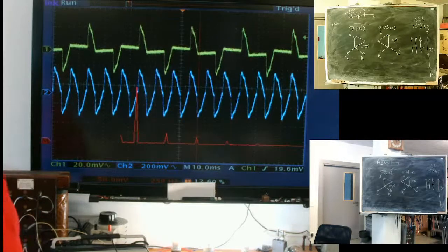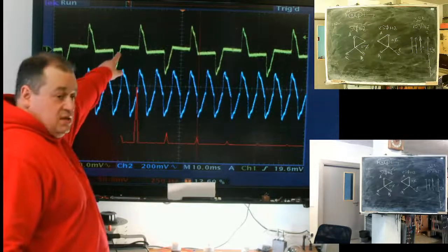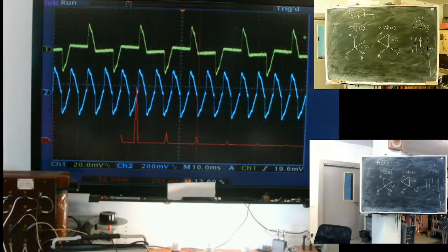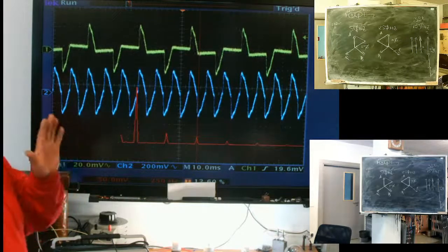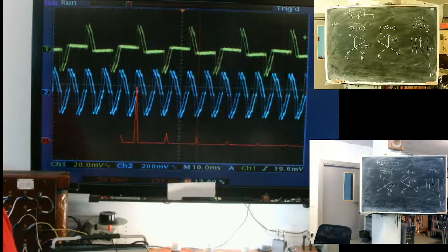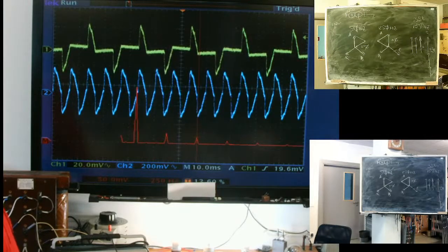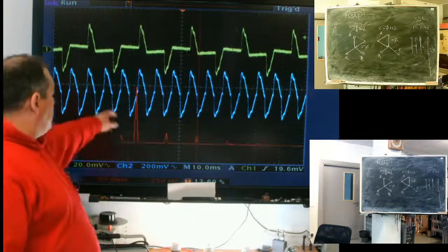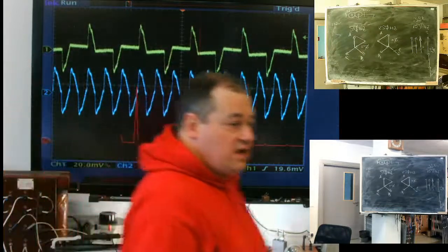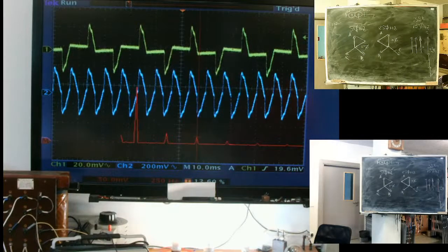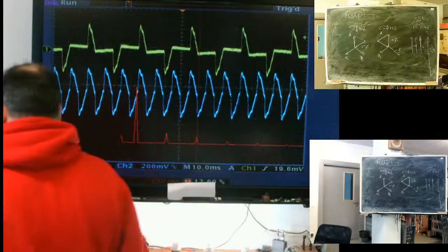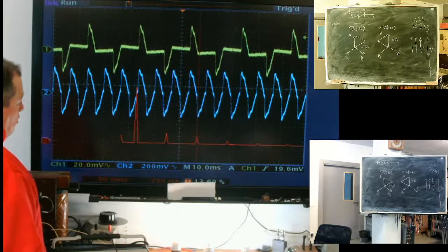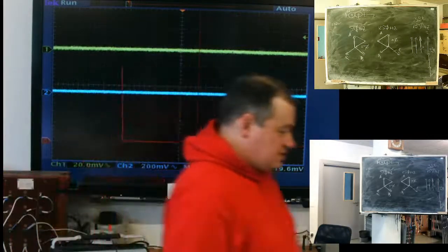Times changed. When a load consumes non-sine current, the laws of electrical engineering are still in force. But you need to understand something from the theory of signals, because this is reality. This is our reality. Not 0, but triple the current of the third harmonic.